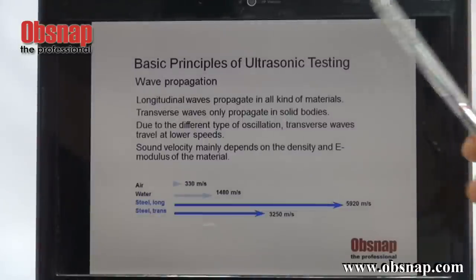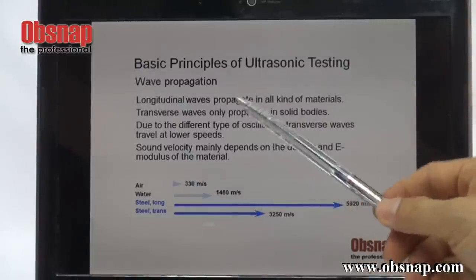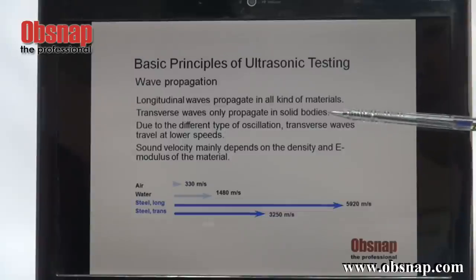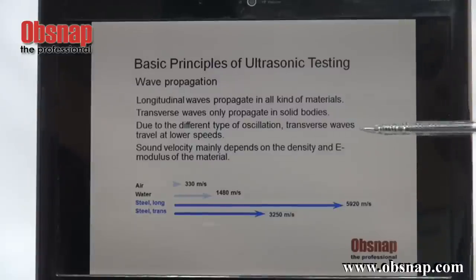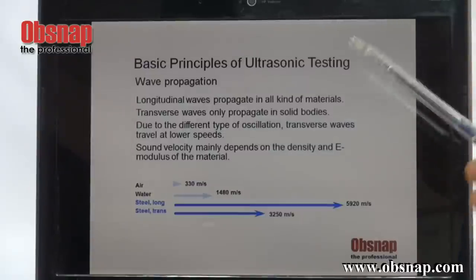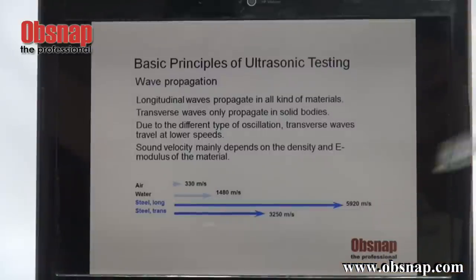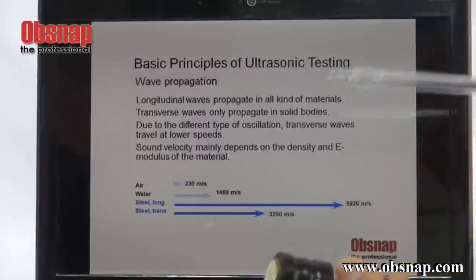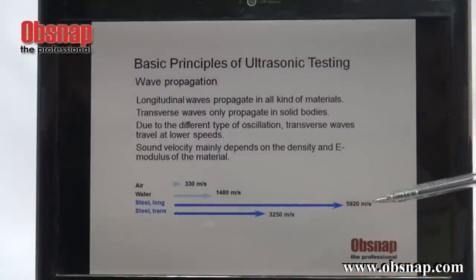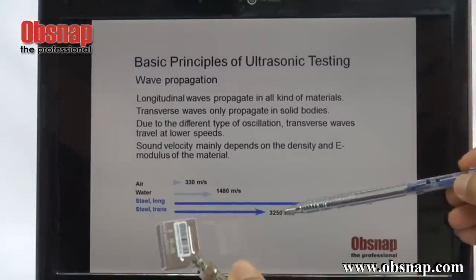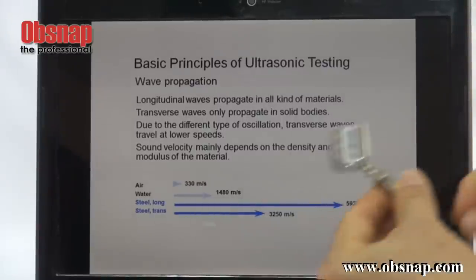About wave propagation: longitudinal wave is actually propagated in all kinds of materials. However, transverse wave only propagates in solid bodies. Due to the different type of oscillation, transverse wave travels at lower speed. For the same material, when using a straight probe, the sound actually travels at the speed of 5,920 meters per second. And transverse speed is only 3,250 meters per second — there's a lot of difference.